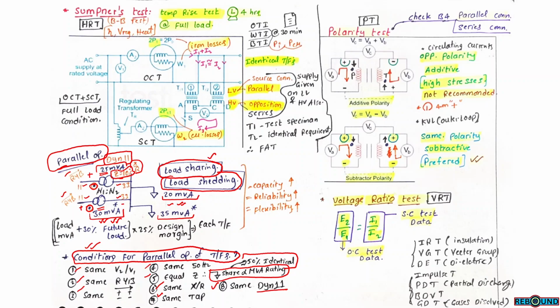So depending upon MVA rating and depending upon the load condition, switching on and switching off the transformers varies as per the load condition. This kind of arrangement is helpful for increasing the capacity of the total system, increasing the reliability, increasing the flexibility. Rating of each transformer: total load MVA plus 30% of future load, multiplied by 25%, which is the design margin. This has to be the rating of each transformer.